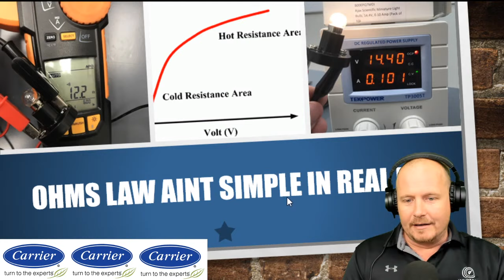All right, so next thing is inductive loads are really tricky. Here's one. I pulled up this particular compressor in the Copeland mobile app, and I looked at the winding resistances. So take a look at the start and run winding resistances on this motor. The run winding in single phase is connected across the line, between L1 and L2, while your start winding is connected between one leg and a capacitor, so the capacitor acts as a limiter.